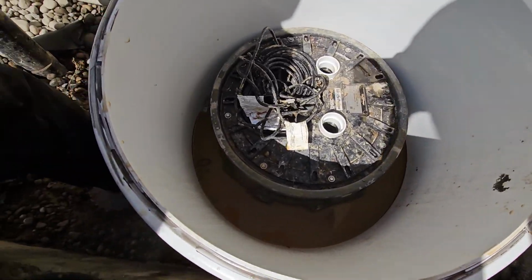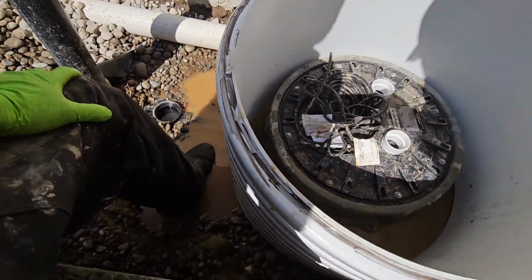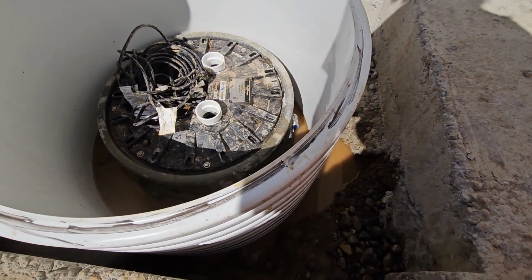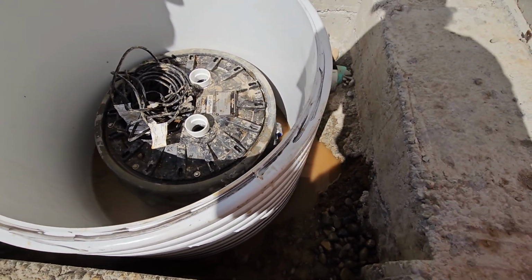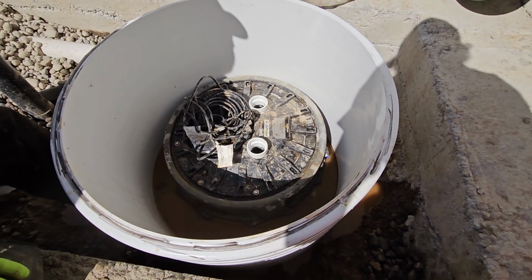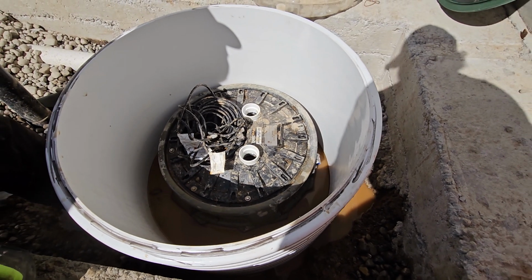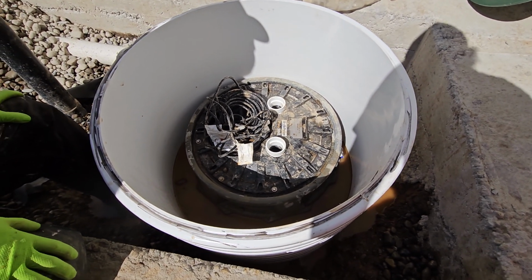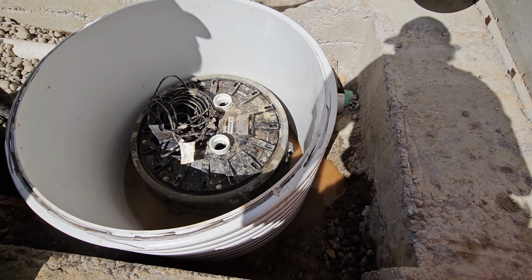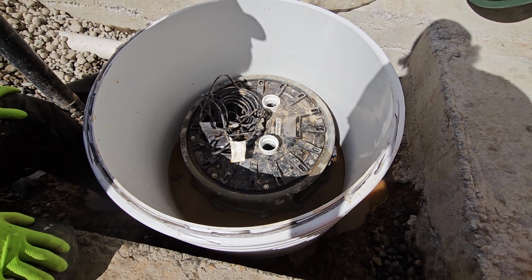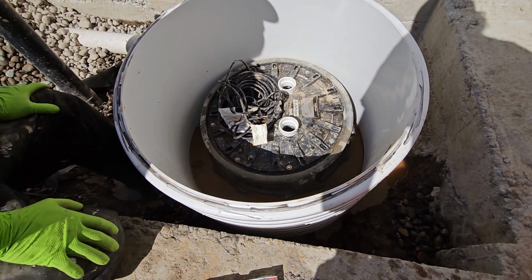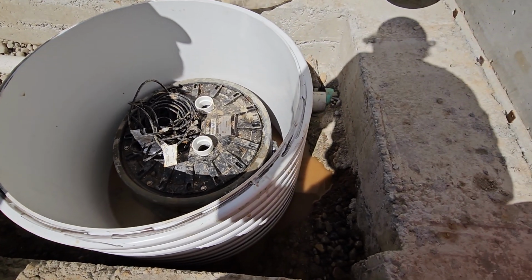Never going away. So this pump basin right here is always going to be in water, and when it's pumped dry, there's going to be a buoyancy force trying to pop that tank out of the ground. So we want to make sure that we have good grab on holding that tank into the ground. And here's our game plan.